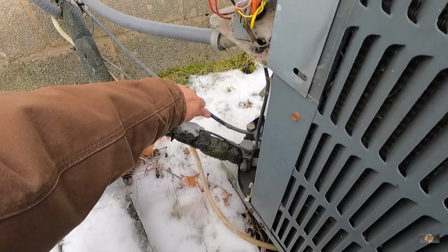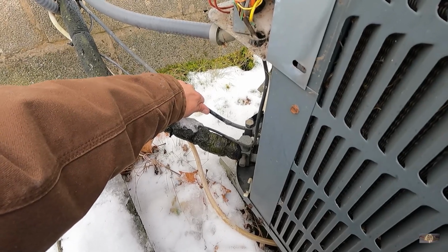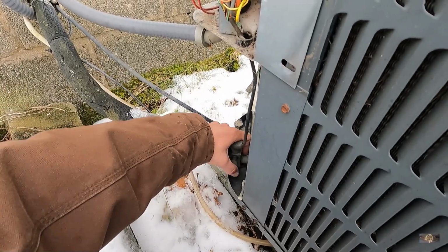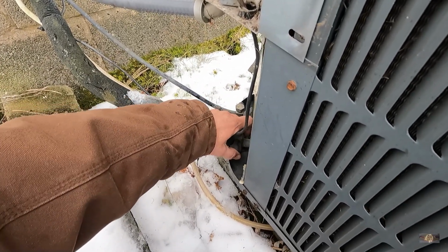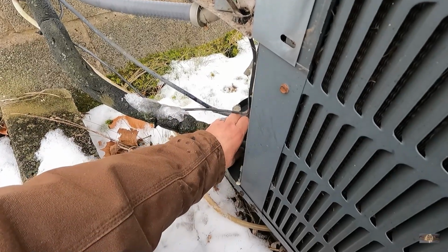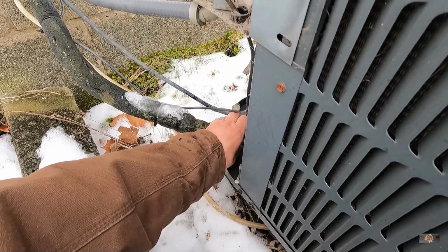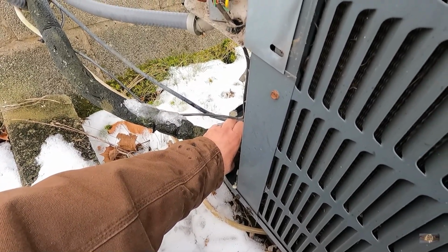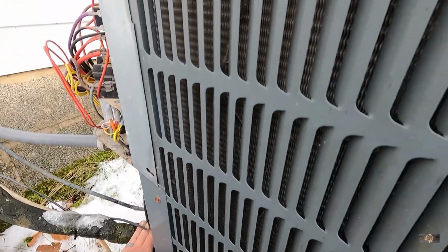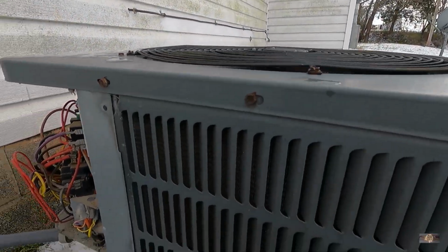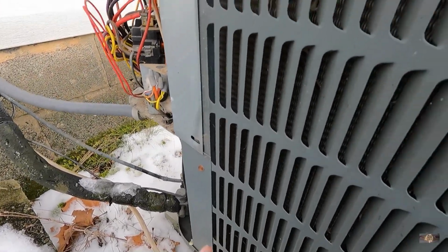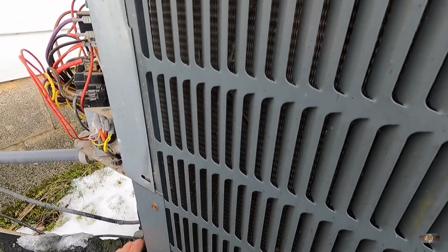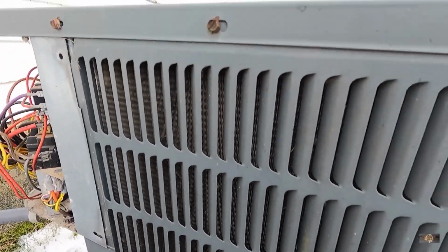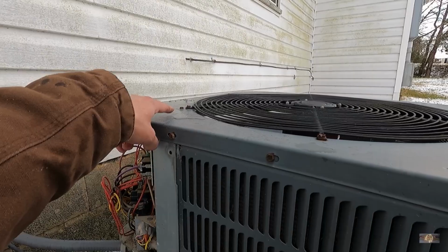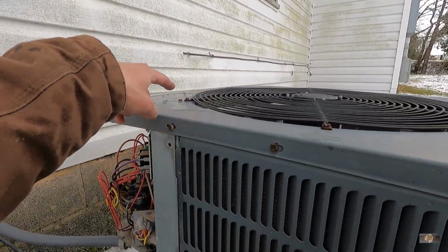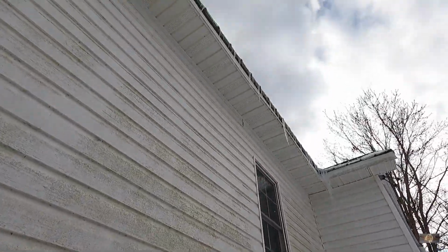I could feel heat here on the liquid line. I could feel some heat on the hot gas line. They don't maintain this system at all. The thing was quiet when it started, and when I came out here I was like, oh, the compressor's not running, but it had already started when I was inside. And look at that, that just fell right on the unit here from up there.